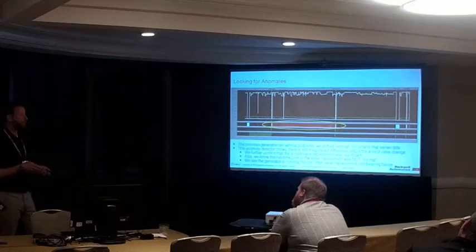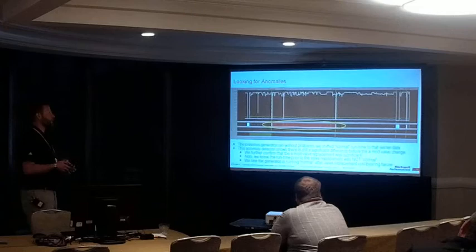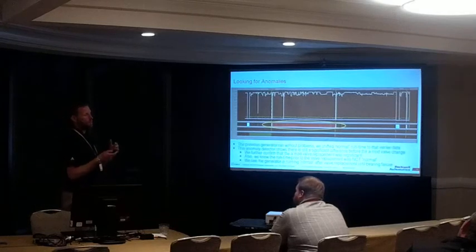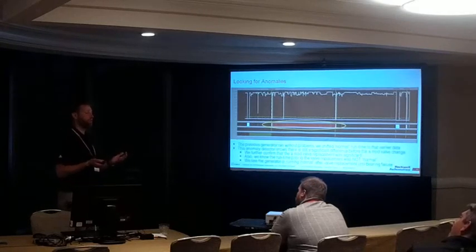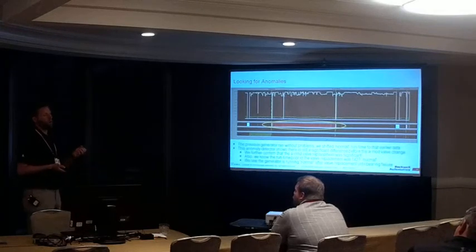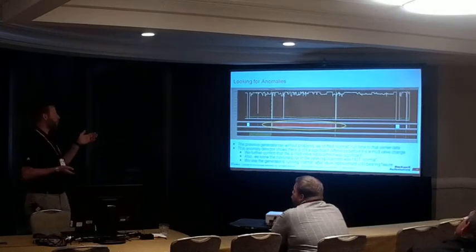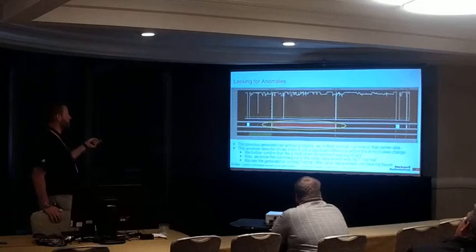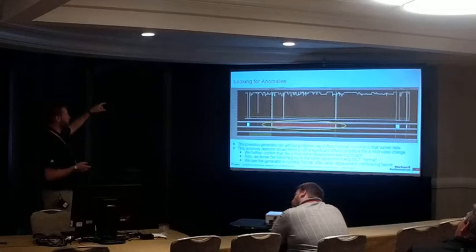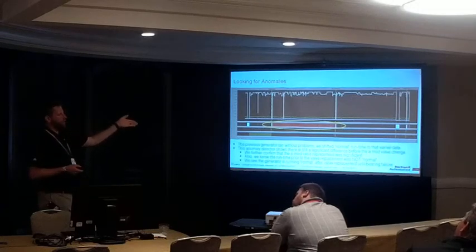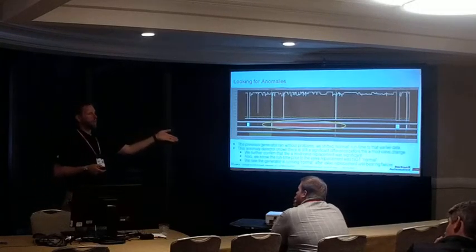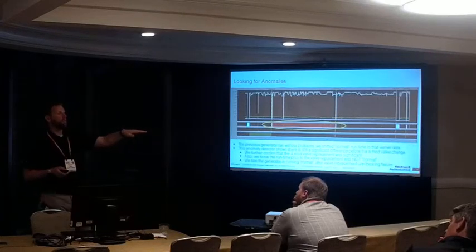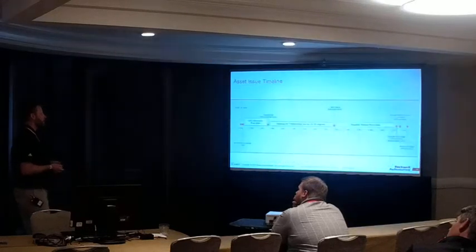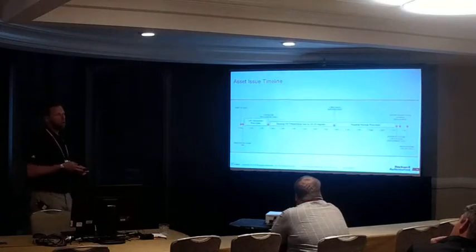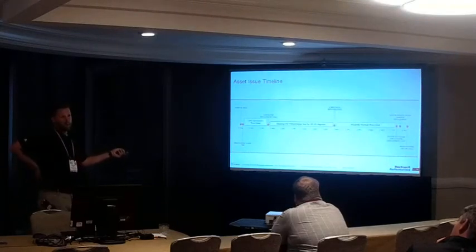We didn't understand, so we dug into the actual data, and that's where we discovered a temperature sensor around the bearing. At first we thought it was faulty, but the data showed the temperature in the bearing slowly dropping day over day, then flatlining, staying continuously low by about 20 to 30 degrees over a six-month time period.